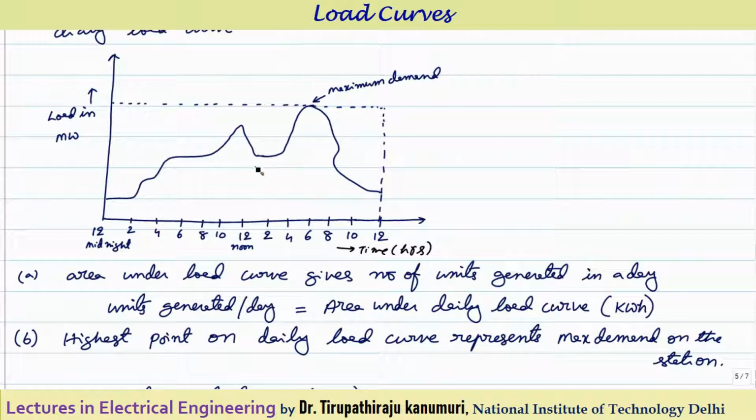And the second one, we always have to maintain some extra spare unit so that in an emergency the continuity of power will not be hampered. For example, if I select a single unit corresponding to maximum demand, I have to keep one spare also, so the cost increases drastically. And the efficiency is also less because the load is continuously varying.